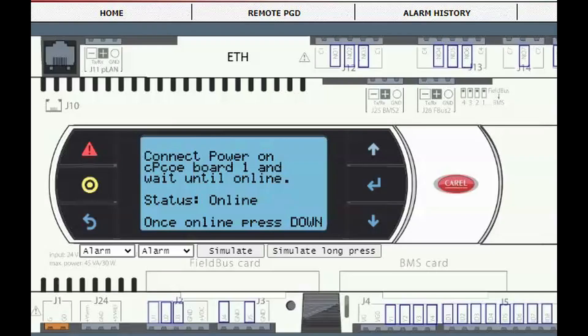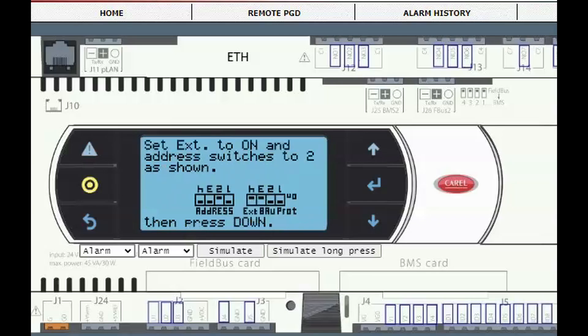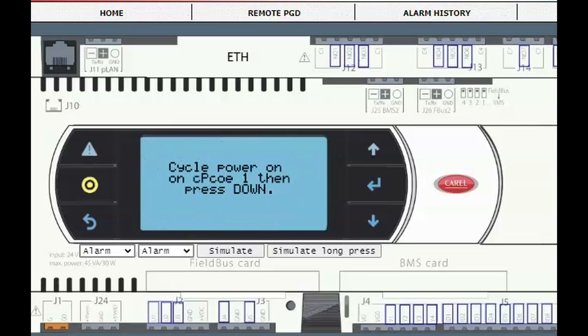Now press down and set the locations of the dip switches to match what is shown on the display. Note, the switch in the black box in the upper position indicates the switch is on. Press down and cycle the power on the new expansion board. Do not turn the power off to the main controller.